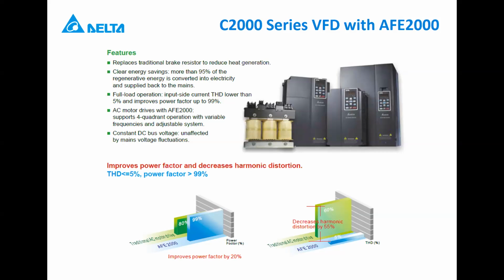This protects your motor and your VFD from voltage fluctuations. With the AFE, you can achieve total harmonic distortion lower than or equal to 5%, and the power factor increases by more than 20% when you use an AFE unit with our C2000 drives.